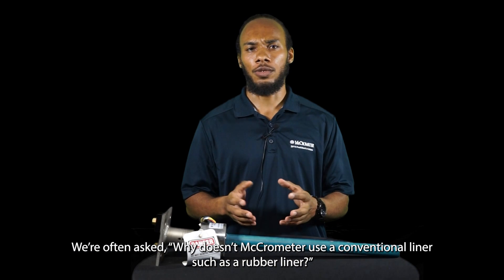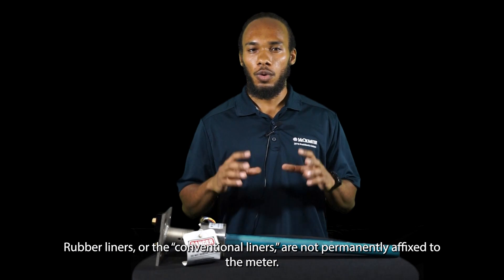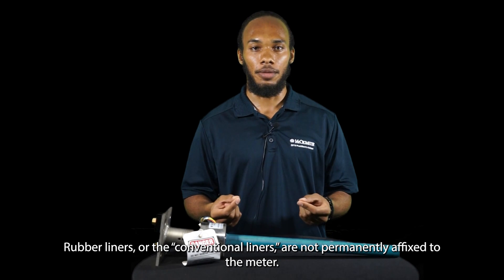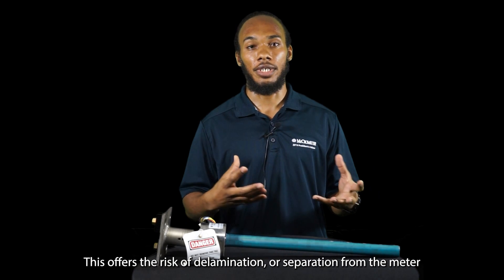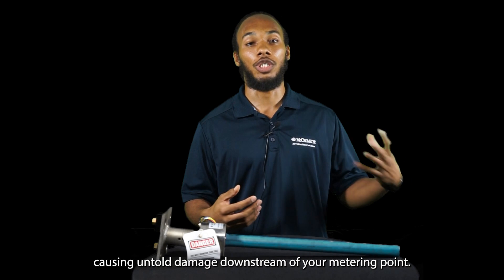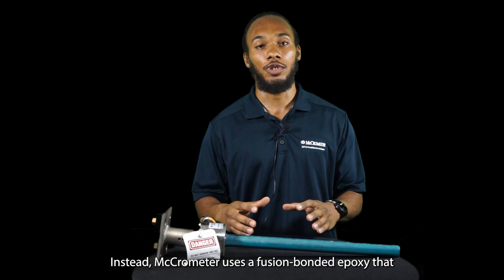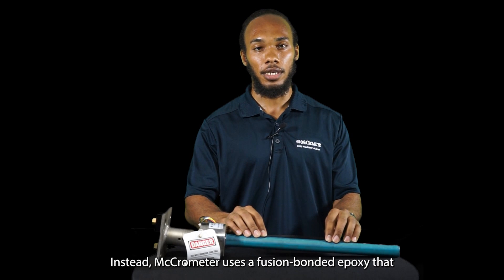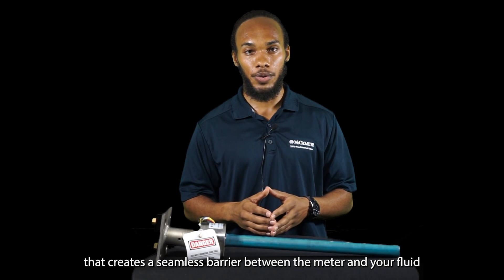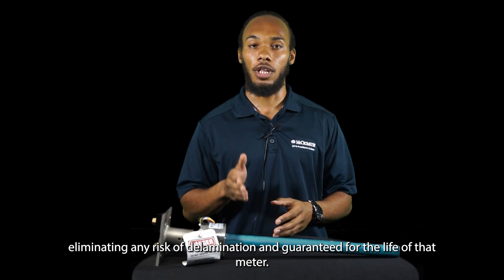We are often asked why McCrometer doesn't use a conventional liner, such as a rubber liner. Rubber liners, or conventional liners, are not permanently affixed to the meter. This offers the risk of delamination or separation from the meter, causing untold damage downstream of your metering point. Instead, McCrometer uses a fusion-bonded epoxy that creates a seamless barrier between the meter and your fluid, eliminating any risk of delamination and guaranteeing it for the life of that meter.